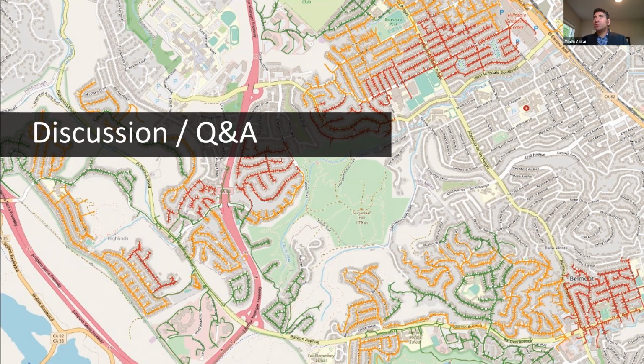Another question we got a bunch of times, so I think we should address it: which software is used to perform the HCA. At least in my work, I've seen CYME and Synergi used most often, particularly because those are distribution modeling software where you can both build a feeder model and perform an HCA analysis. I also see a lot of investor-owned utilities using the EPRI DRIVE software, but DRIVE doesn't build the feeder models, it just performs the hosting capacity analysis. So you have to use different distribution modeling software to build the feeder models, and that creates an extra step to transfer the feeder models to DRIVE for the analysis.